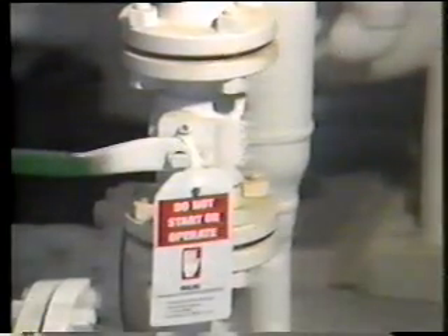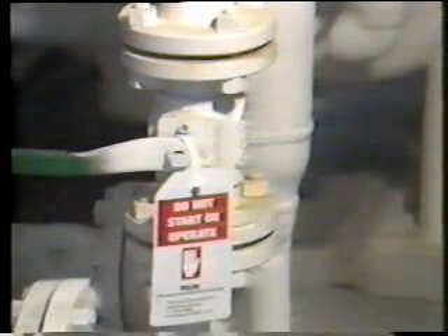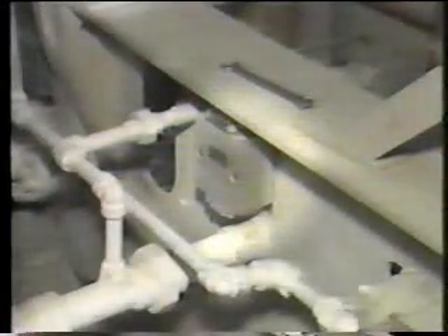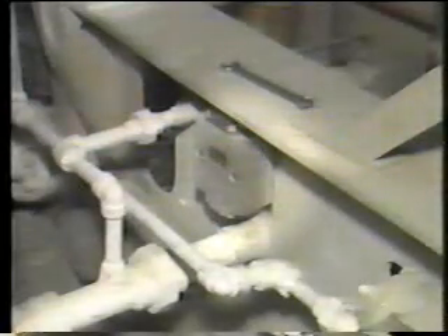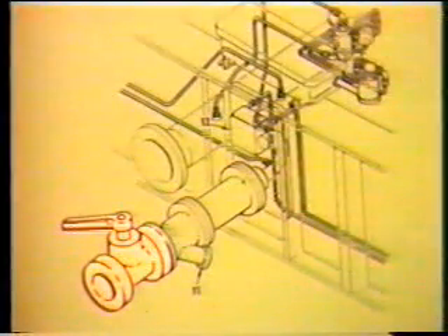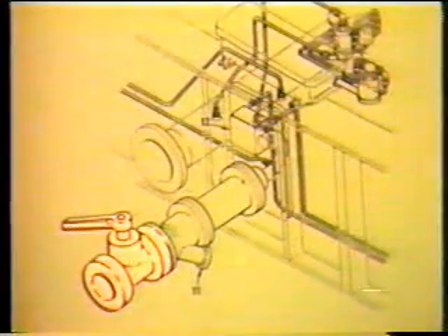Prior to any disassembly of system components, the pressure must be let down. Gas will be trapped between the manual shutoff and the primary shutoff valves. Pressure will also be trapped in the pilot gas system, which is supplied ahead of the primary fuel shutoff valve. Install a flexible line between the fuel gas strainer and the overboard gas vent system manifold. Pressure from the gas supply line should not be allowed to escape in the area of the package.